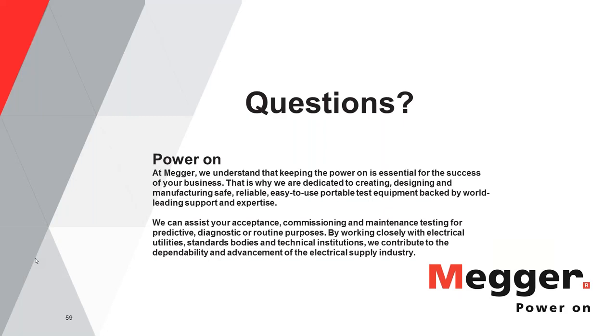So the question might be interpreted in two different ways. For low voltage circuit breakers that have those coils, if you just want to test the breaker on the coils, there's another technique that is the secondary injection test. For that, you need specific accessories for the breaker. You need proprietary testing equipment from the manufacturer of the breaker. So you will have to have different testing equipment for different breakers.